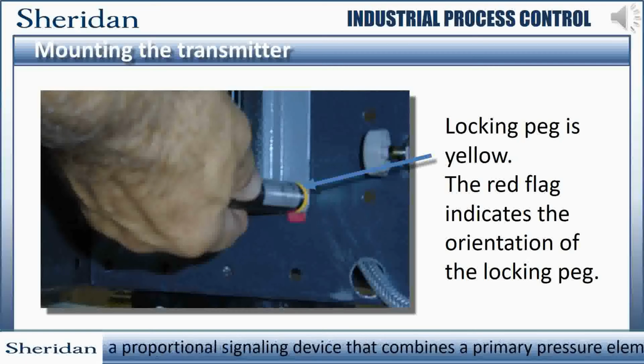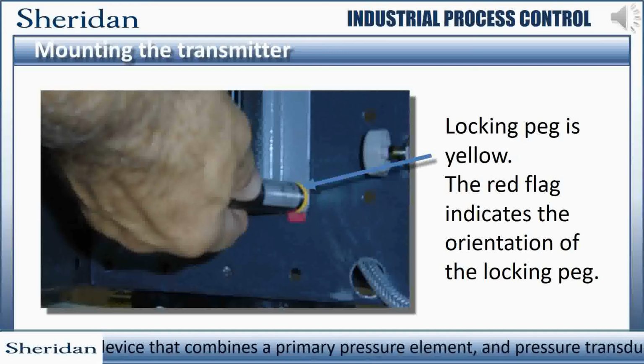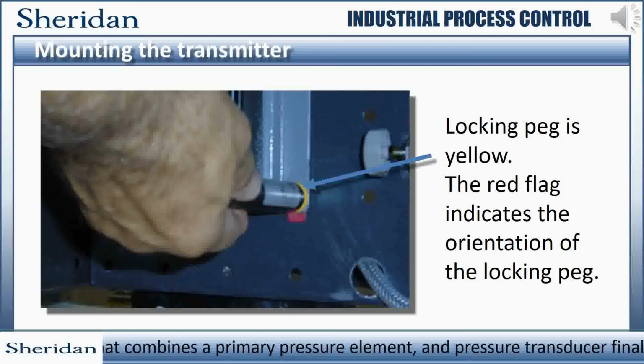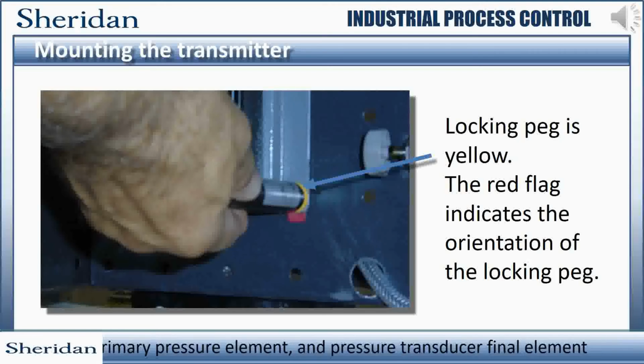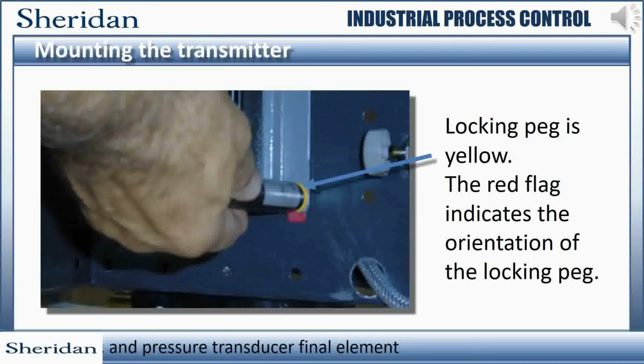Begin by securing the transmitter where it needs to be. In field work, this may be the same location as a transmitter you are replacing, while in new installations, be sure to follow any blueprints and mounting instructions provided by the manufacturer. Since location is critical to correct operation, be sure to double-check any instructions, and if any doubt remains, ask the appropriate person in charge. In our case, the transmitter will be mounted on the metal pegboard as indicated. Use the magic peg wand on the yellow banded peg and rotate 90 degrees clockwise until the red flag disappears. Then check that the device will not move.